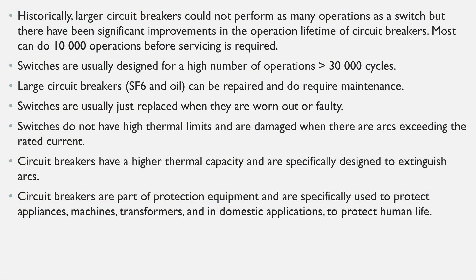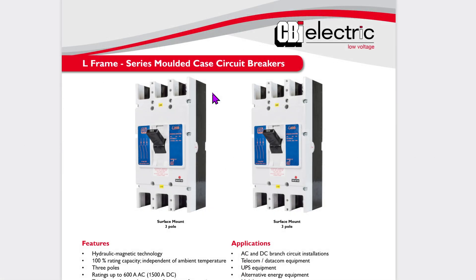Historically, larger circuit breakers could not perform as many operations as a switch, but there have been significant improvements in the operational lifetime of circuit breakers. Most can do 10,000 operations before servicing is required, though it depends on the type. Circuit breakers used in domestic applications tend to have a far higher mechanical and electrical cycling than high voltage and high current circuit breakers.